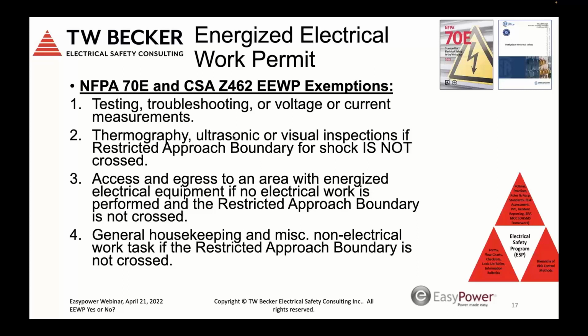All right, now when I talk about the work tasks, 70E under arc flash risk assessment and Z462 under arc flash risk assessment have work task tables. It's table 130.5C in 70E or table 2 in Z462. There's 31 work tasks in that table. And really what I recommend is that we use those work tasks, and based on, again, the justification of equipment design, we add additional exemptions to work tasks that due to equipment design, well, why do we need the permit? We have to do that work task in an energized state because we can't establish an electrically safe work condition before we actually complete that work task.